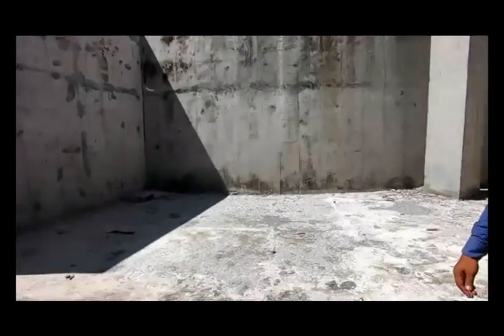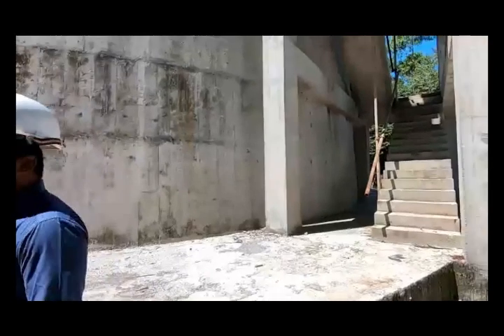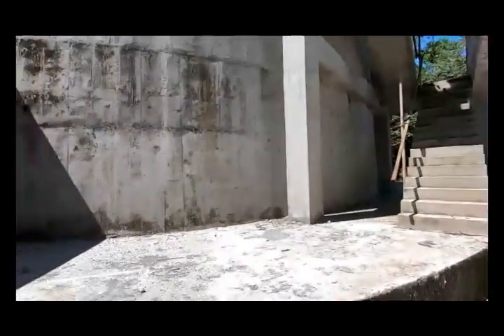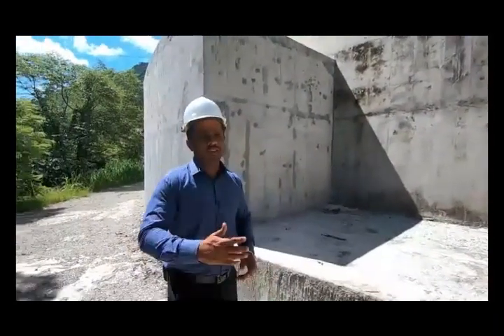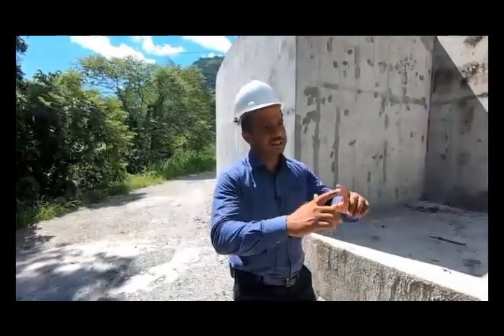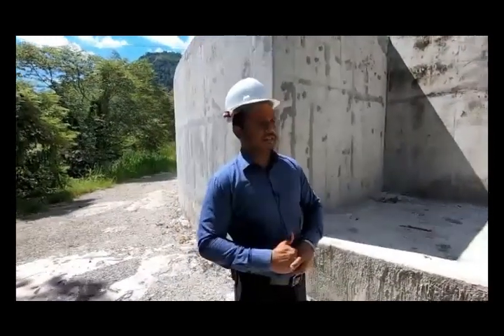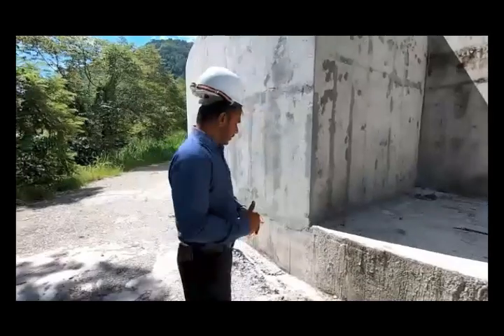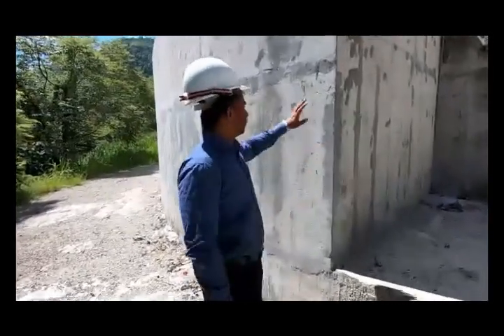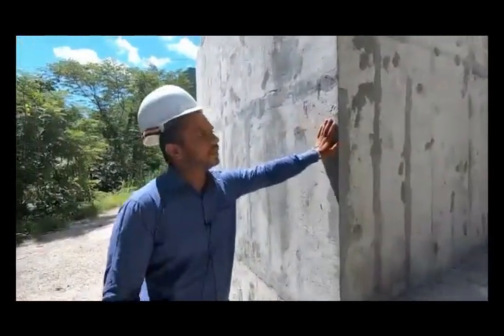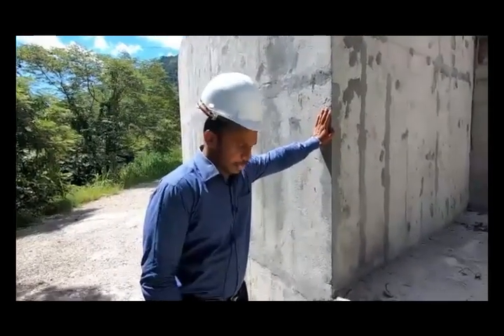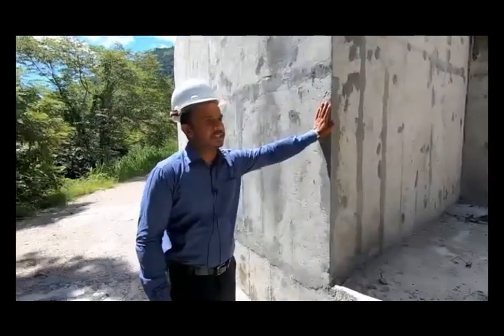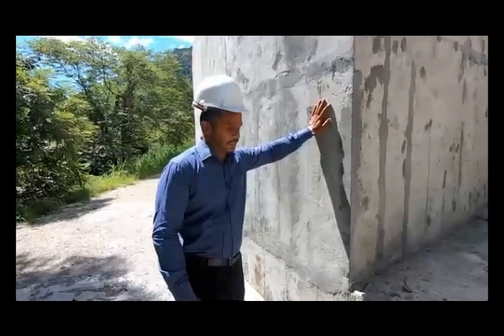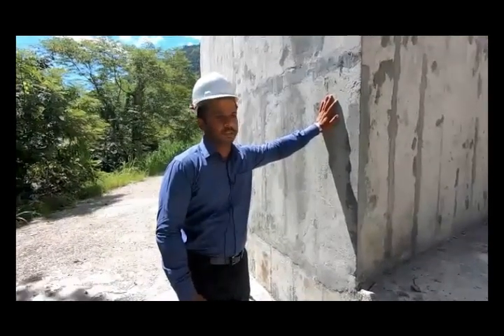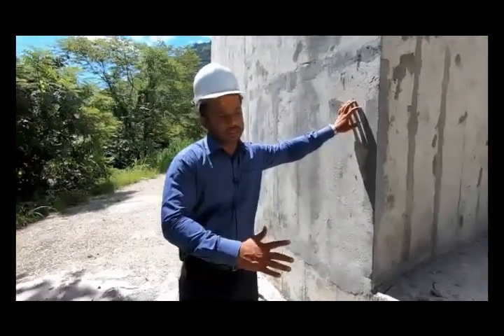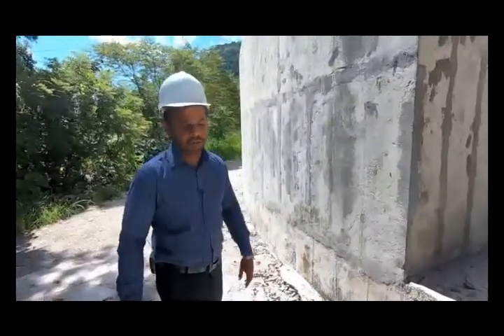Another very important thing we did, especially for our project, is the firefighting facilities at the powerhouse. Previously, we designed a separate tank for this, but we changed the design and attached a fire pool built onto the surge chamber. According to our calculations, this provides 240 cubic meters for all firefighting purposes at the powerhouse.